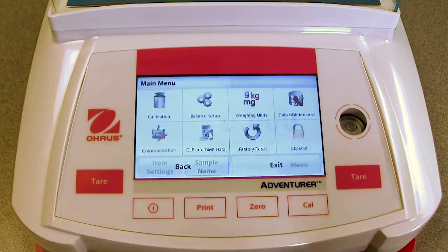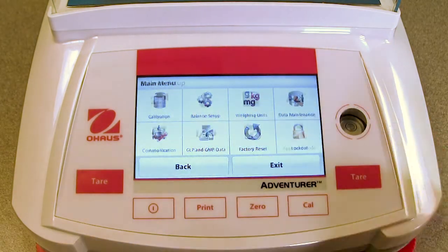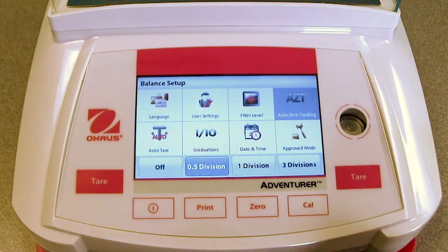The auto zero tracking is used to set the automatic zero tracking functionality. Off is disabled. At 0.5 division, the display maintains 0 up to a drift of 0.5 graduation per second. At 1 division, the display maintains 0 up to a drift of 1 graduation per second. And at 3 division, the display maintains 0 up to a drift of 3 graduations per second.